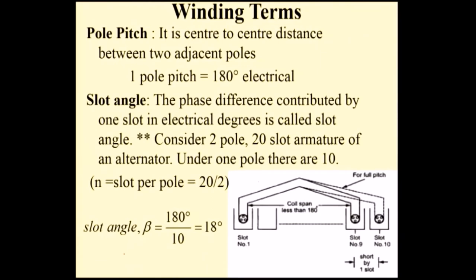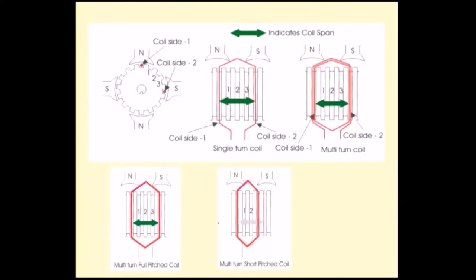Slot angle is the phase difference contributed by one slot in electrical degrees. Consider a 2-pole generator with 20 slots: slot per pole is 20 divided by 2, which equals 10. The slot angle formula is β = 180°/n, which gives 18 degrees in this case.